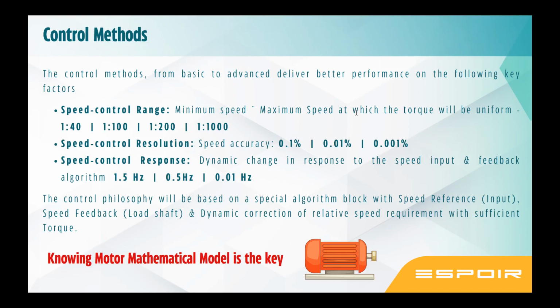In a closed loop application, you get much better. In a servo application, you get much better. The speed control range in a servo application is considered as 1:5000. Means you can control within a RPM within a degree. You can just move a motor 1 degree, carrying full load, full torque, and stop within that 1 degree. The acceleration takes place, run command you get, you move, you stop at 1 degree. All happens within 1 degree. So that is the precision you can achieve in a servo motor.